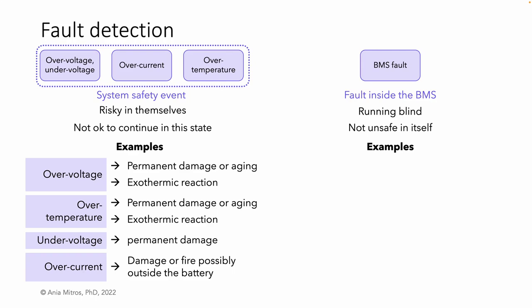Now let's look at some examples of BMS faults. A disconnected sense wire is a common one. Connectors connect, and sometimes they disconnect. A loose connector or broken wire is not dangerous in itself. It won't propagate to cause fire or other collateral damage. However, if we allow further charge or discharge, we cannot monitor to ensure that we avoid a system safety event.